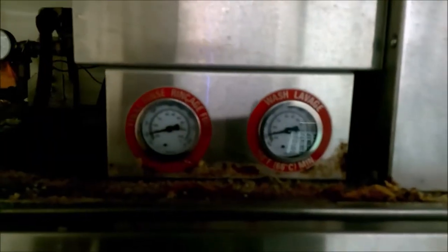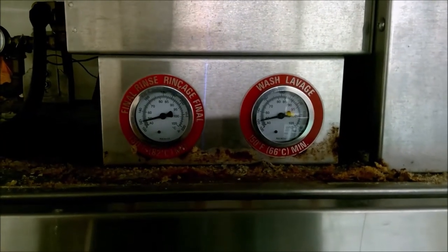Now we're going to check our visual cues before we go to the schematic. First thing you can see the wash temperature is not increasing from 120 and that contactor plunger is not pulling in for our tank heater.